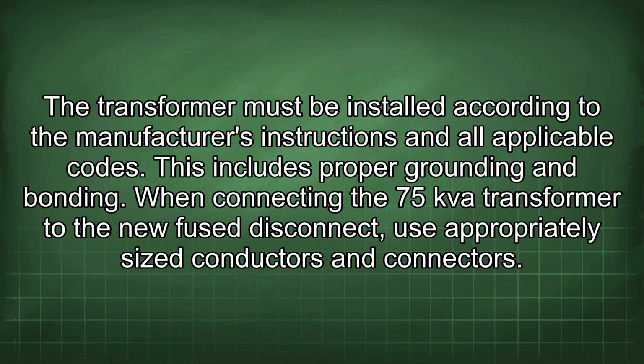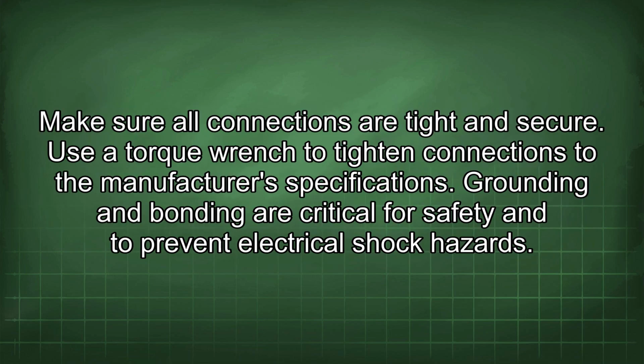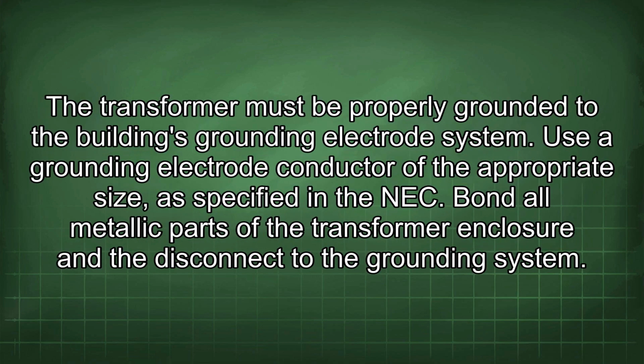When connecting the 75 kVA transformer to the new fuse disconnect, use appropriately sized conductors and connectors. Make sure all connections are tight and secure. Use a torque wrench to tighten connections to the manufacturer's specifications. Grounding and bonding are critical for safety and to prevent electrical shock hazards. The transformer must be properly grounded to the building's grounding electrode system. Use a grounding electrode conductor of the appropriate size, as specified in the NEC. Bond all metallic parts of the transformer enclosure and the disconnect to the grounding system.